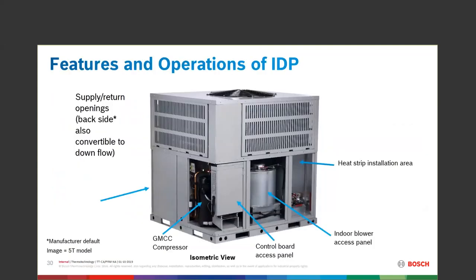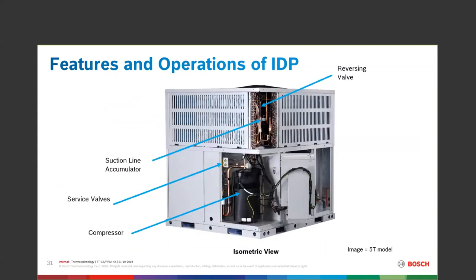A couple of pictures of the machine. When I looked at it for the very first time and took the panels off as an old contractor, I was very pleased with how the system was laid out and the accessibility — I didn't have to remove something to get to something else. Very easy to look at and get to. The reversing valve, accumulator, and all the refrigeration components were basically behind one panel: remove it and there they were.